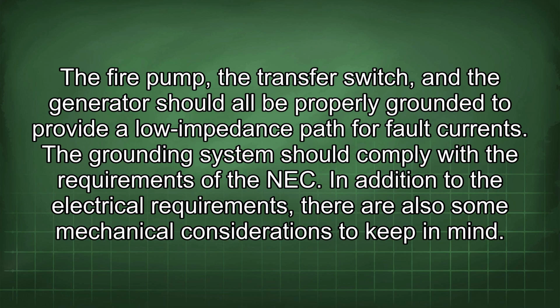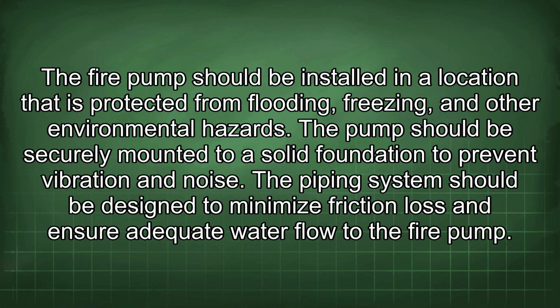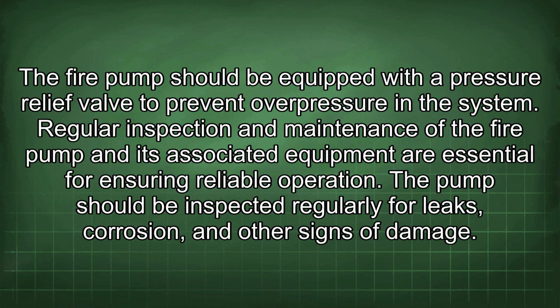In addition to the electrical requirements, there are also some mechanical considerations to keep in mind. The fire pump should be installed in a location that is protected from flooding, freezing, and other environmental hazards. The pump should be securely mounted to a solid foundation to prevent vibration and noise. The piping system should be designed to minimize friction loss and ensure adequate water flow to the fire pump. The fire pump should be equipped with a pressure relief valve to prevent overpressure in the system.